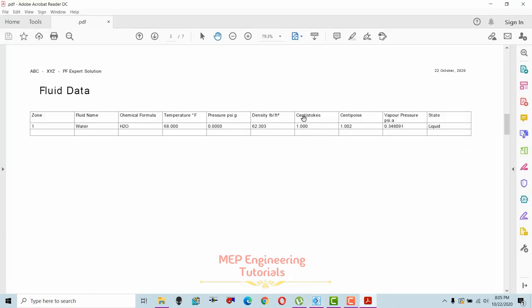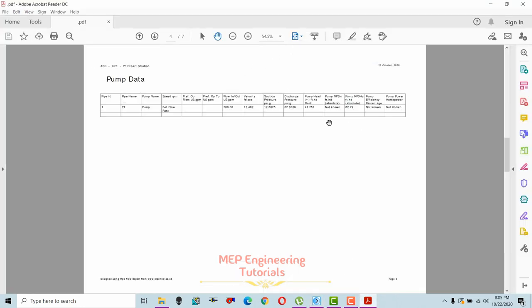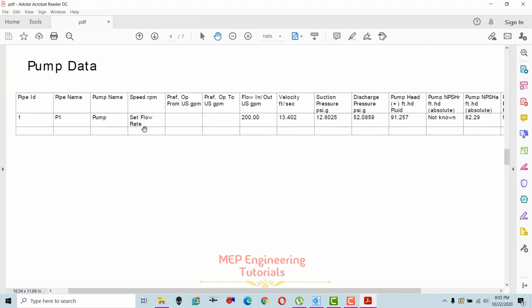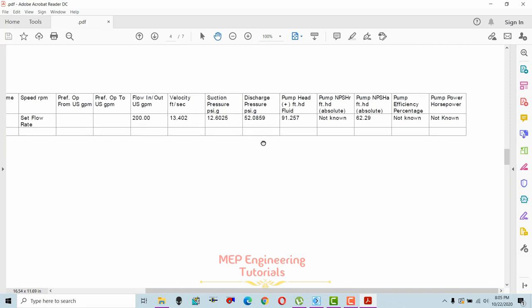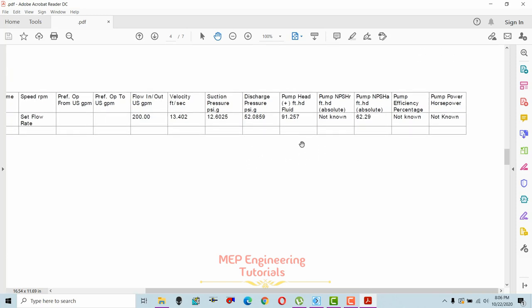In the PDF report, the pump data section shows: pump flow rate of 200 gpm, velocity of 13.402 ft/s at the main pipe, suction pressure of 12.6 psi, discharge pressure of 52.08 psi, and pump head of 91.257 feet. The NPSHr (net positive suction head required) should be checked with the pump supplier, and NPSHa (available) is calculated as 62.29 feet.